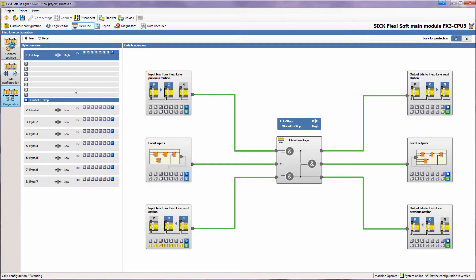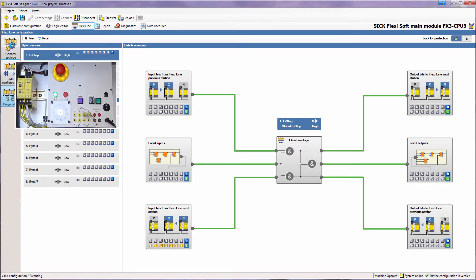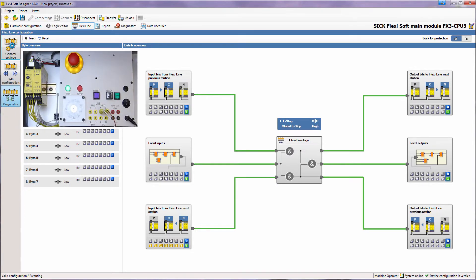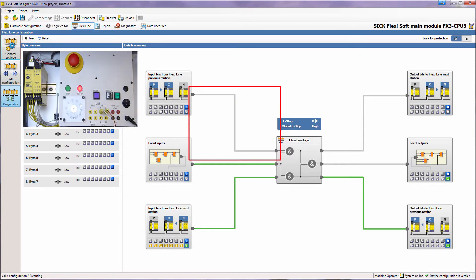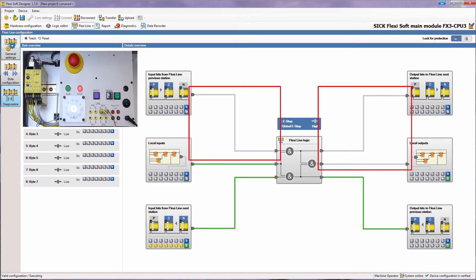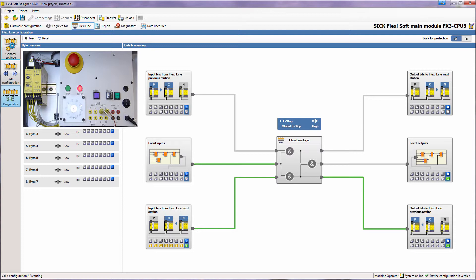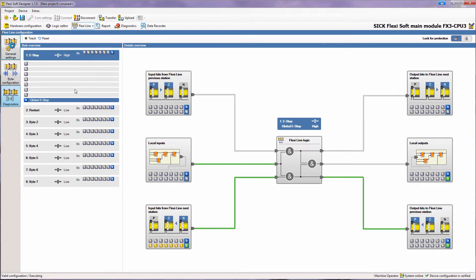Let me also show you what happens if I press the e-stop on the previous station. Now this input bit as well as all the output bits change to low and the actuators of all demo cases stopped. We know now for sure that the global e-stop function which we implemented in the last tutorial works as we intended it.